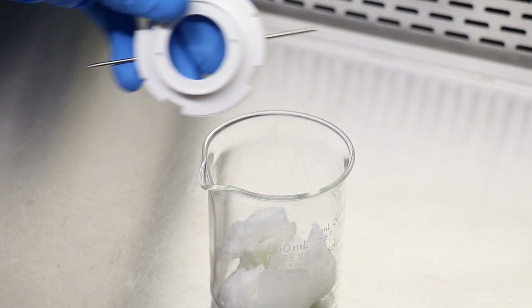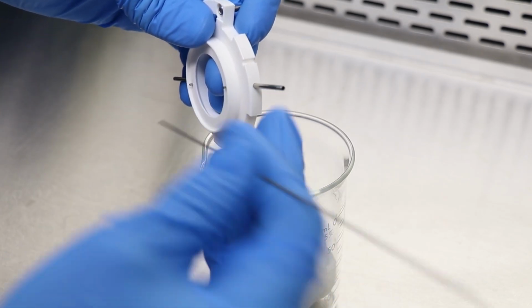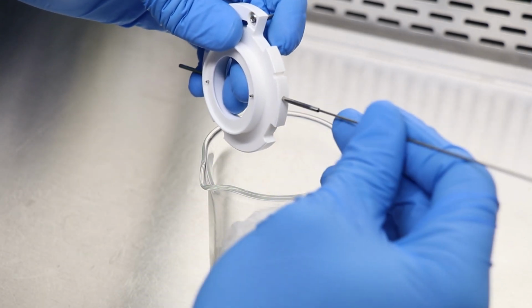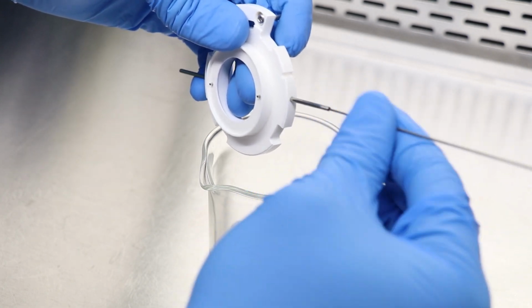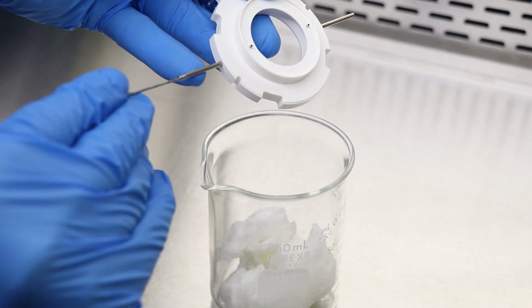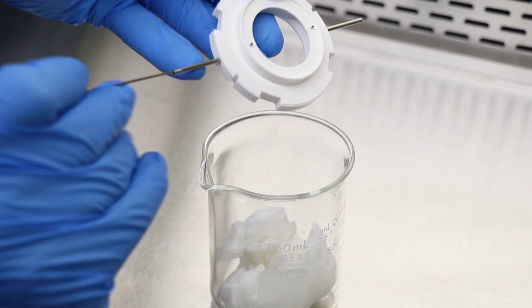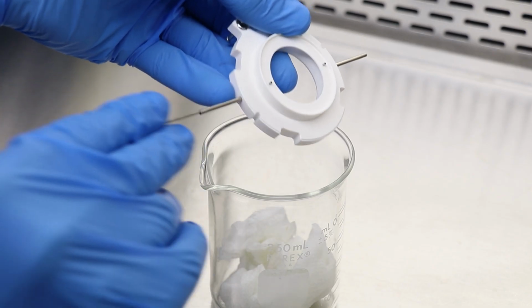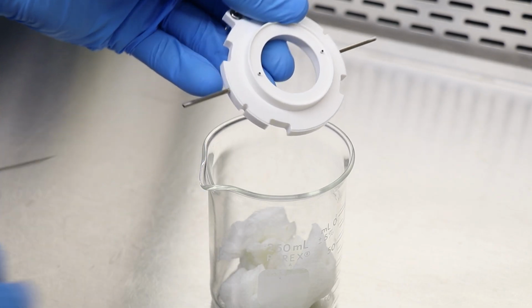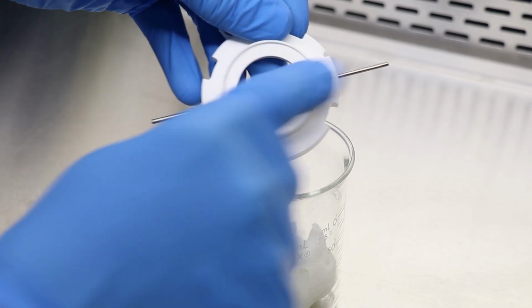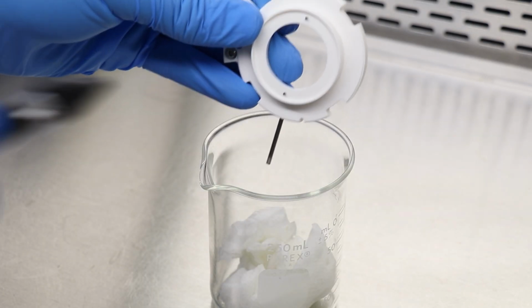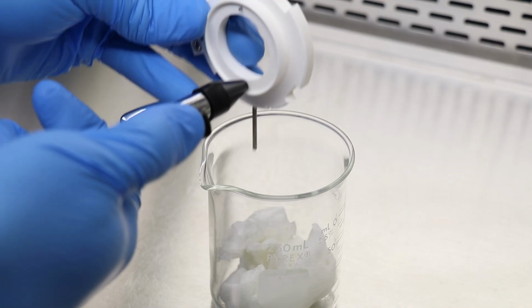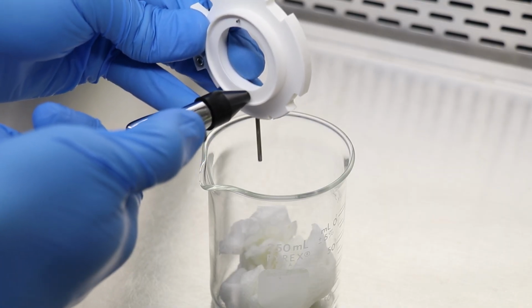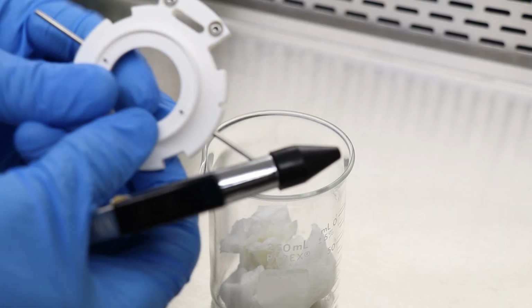If there is still a blockage, as a last resort, it would be time to use a mechanical device inside the port. Start with another 15 minutes in the sonicator. Then, using a small wire or similar device, gently agitate and rotate in the port. Try not to push the clog all the way into the port. You are only trying to release any items inside it. Purge with air after agitation is complete from the small side to the large tubing.